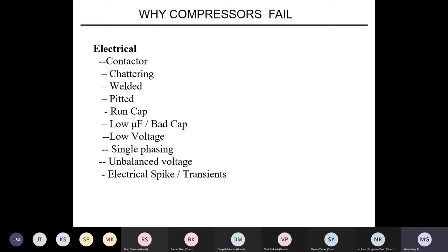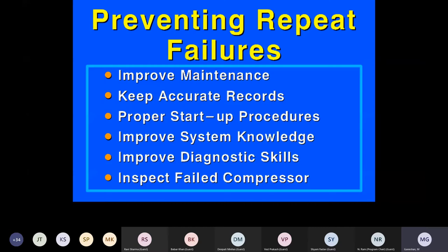So you can see these are all the electrical causes which can lead into failures. So, preventing the repeat failures: improve the maintenance and keep accurate records. Why? Because we can see the trend. How low did the suction go, how many days, when did it start going low? Why does the discharge keep going so high, and since when?